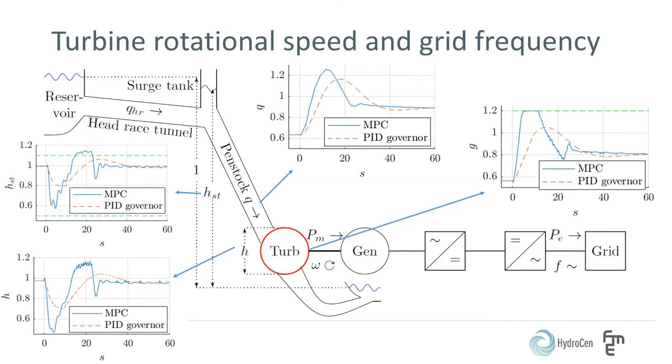The disadvantages of the MPC is that it causes additional oscillations in the hydraulic system, both low frequency oscillations between the reservoir and surge tank, called mass oscillations and higher frequency oscillations, called water hammering, as we see here from the two figures of the pressures in the system.